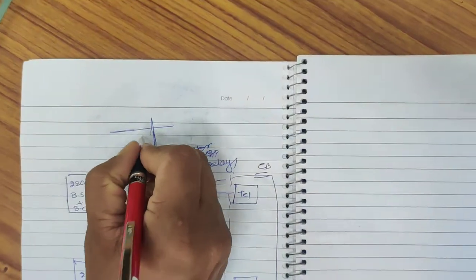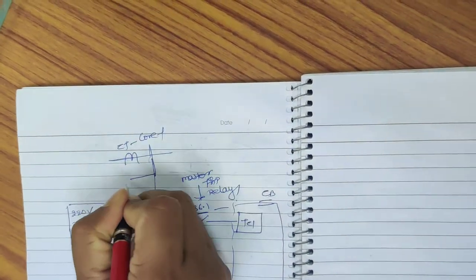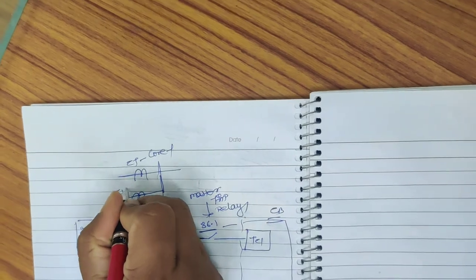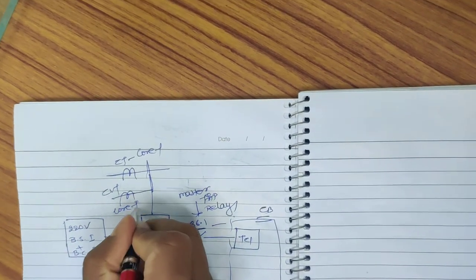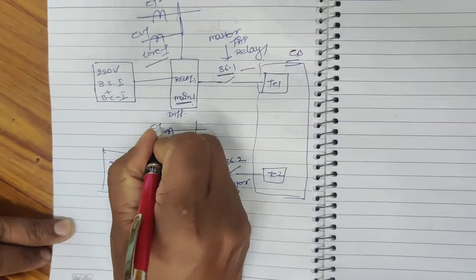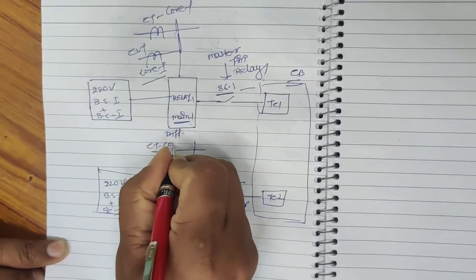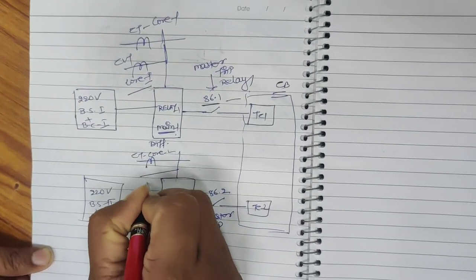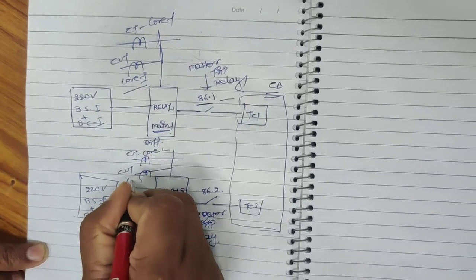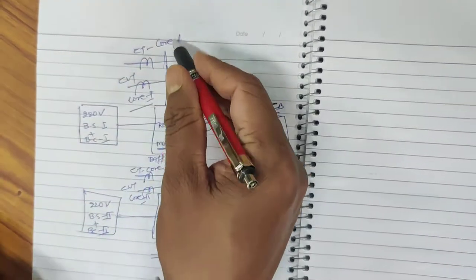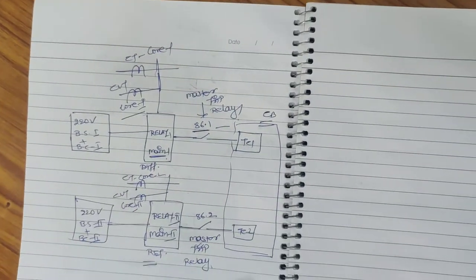Relay 1 receives its input from CT Core 1 and CVT Core 1, if it is for line protection. Similarly, Relay 2 receives input from CT Core 2 and CVT Core 2 for transmission line protection. For ICT and reactor protection, we will have CT inputs from two different cores, but CVT may not be required.